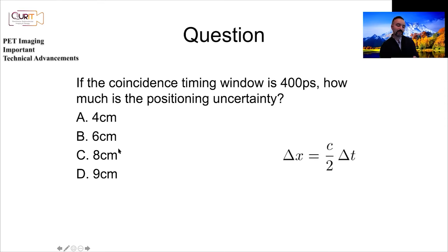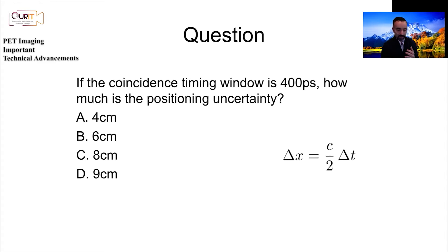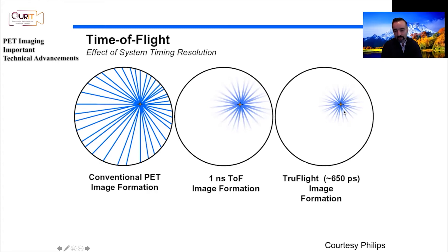The key point is that current timing windows give centimeter-scale uncertainty — not millimeters. So we are not narrowing down to one or two millimeters, we still need to do reconstruction, and we are not directly improving spatial resolution. What we are doing is propagating noise less. With a 200-picosecond camera, the positional uncertainty drops to about 3 centimeters.